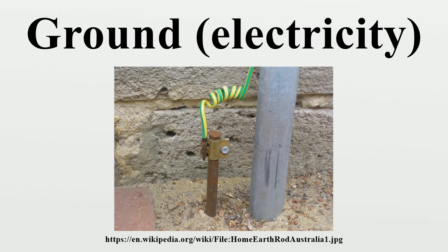Impedance grounding. Distribution power systems may be solidly grounded, with one circuit conductor directly connected to an earth grounding electrode system. Alternatively, some amount of electrical impedance may be connected between the distribution system and ground, to limit the current that can flow to earth. The impedance may be a resistor or an inductor. In a high-impedance grounded system, the fault current is limited to a few amperes. A low-impedance grounded system will permit several hundred amperes to flow on a fault. A large solidly grounded distribution system may have thousands of amperes of ground fault current. In a polyphase AC system, an artificial neutral grounding system may be used.